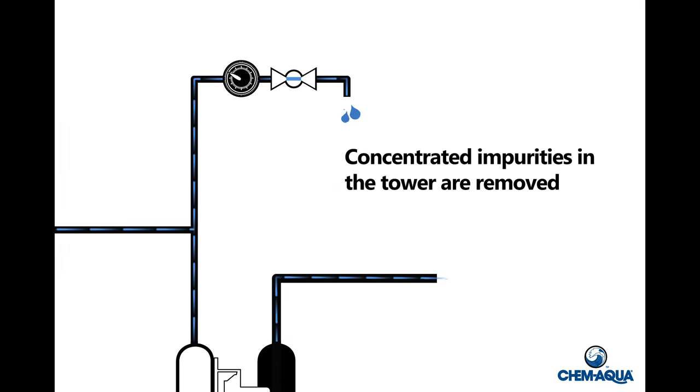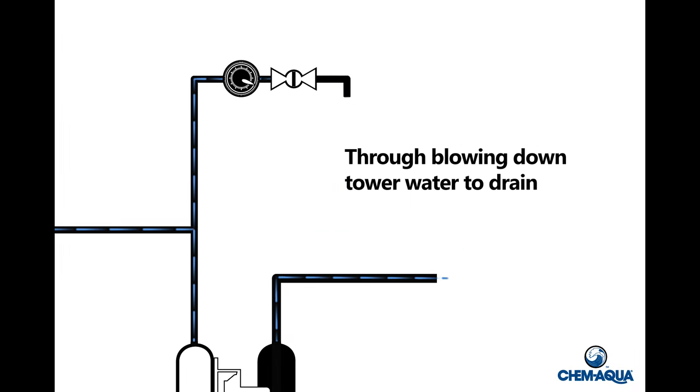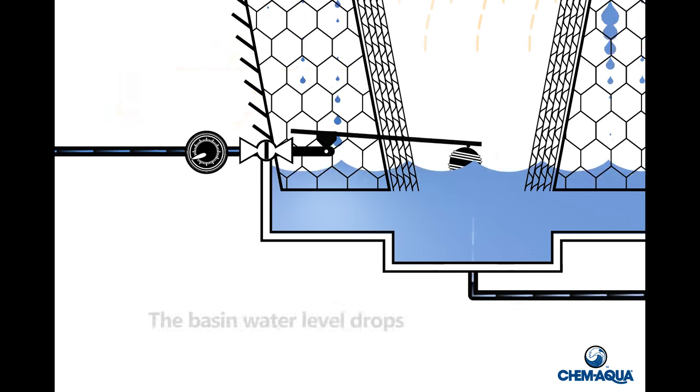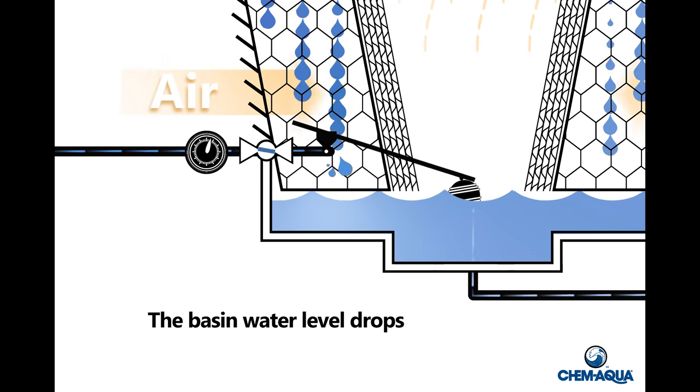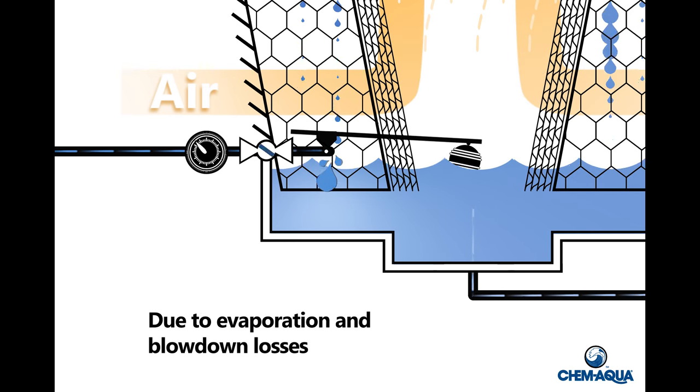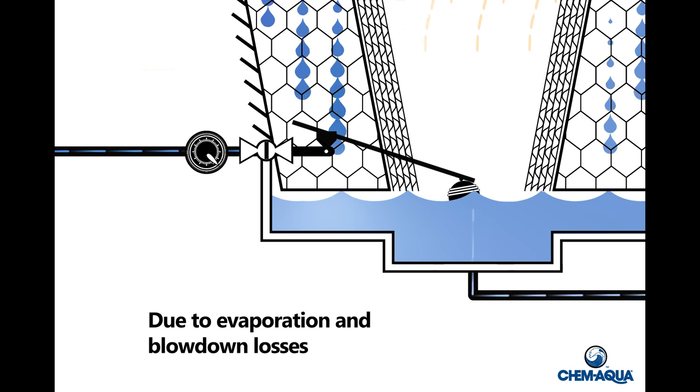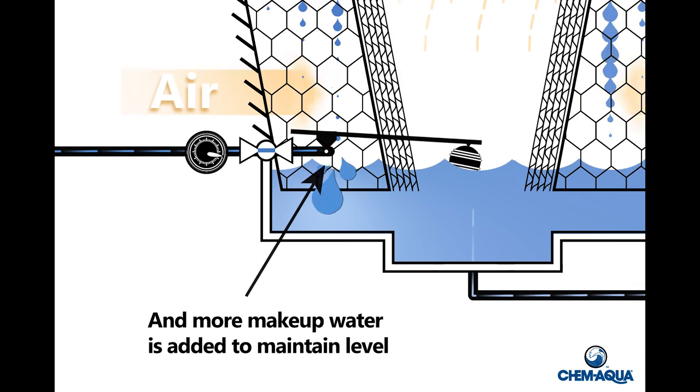Concentrated impurities in the tower are removed through blowing down tower water to the drain. The basin water level drops due to these evaporation and blowdown losses, and more makeup water is added to maintain level.